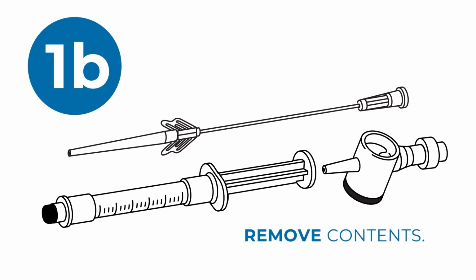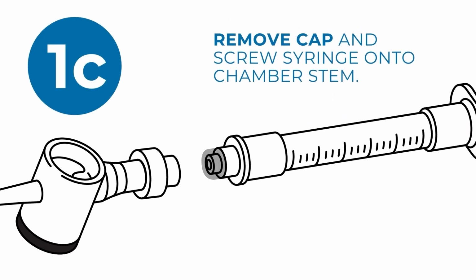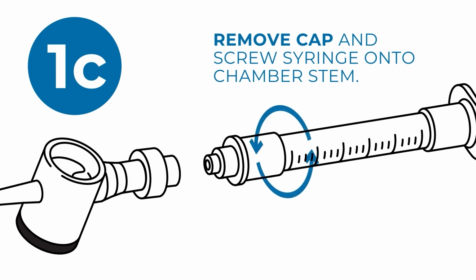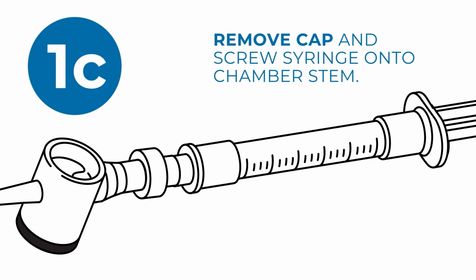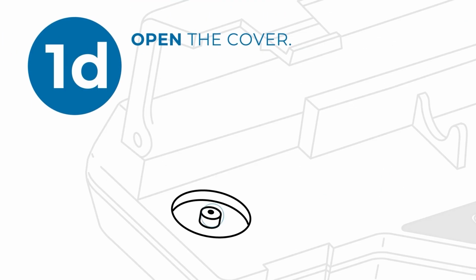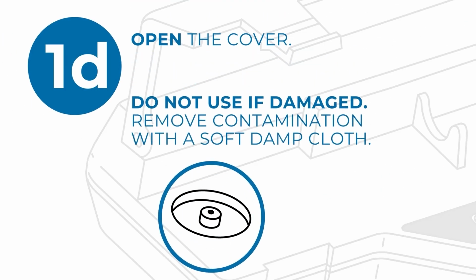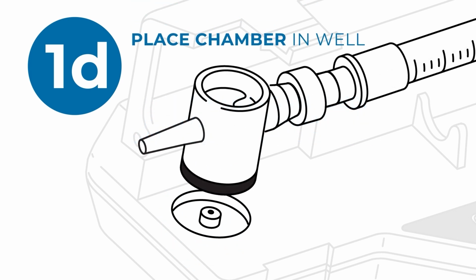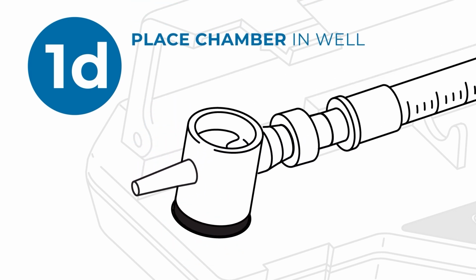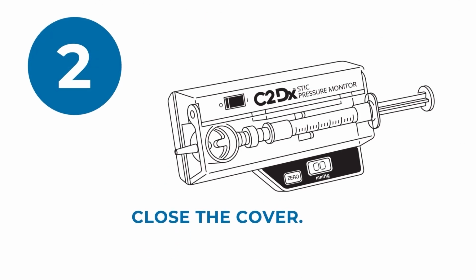Using sterile technique, remove the contents of the disposable pouch, remove the cap on the pre-filled syringe, and screw the syringe onto the chamber stem. Be sure not to contaminate the fluid pathway. Open the cover and inspect the transducer port for damage or contamination. Next, place the chamber into the well with the black surface down. Close the cover, but don't force it.